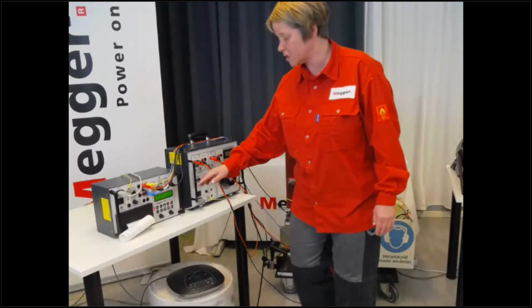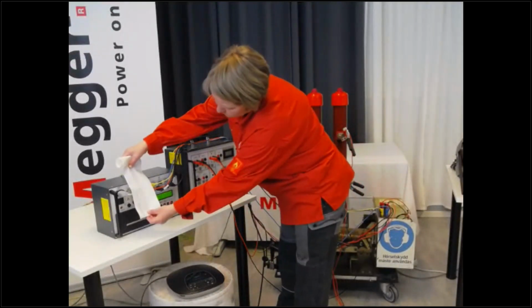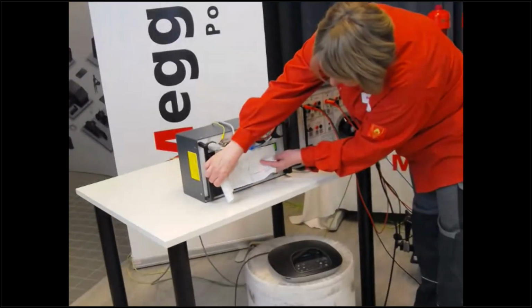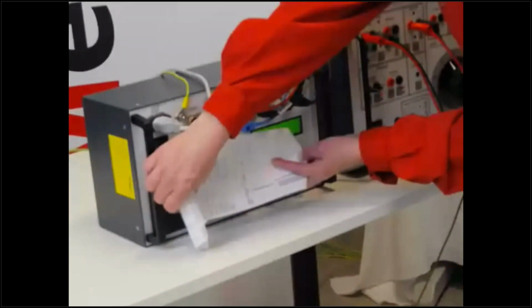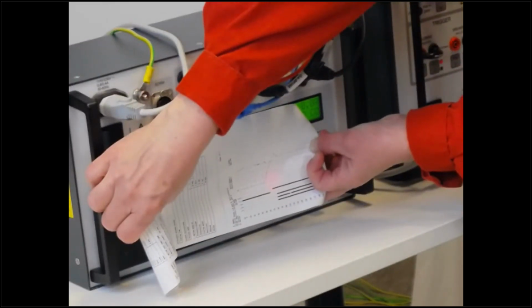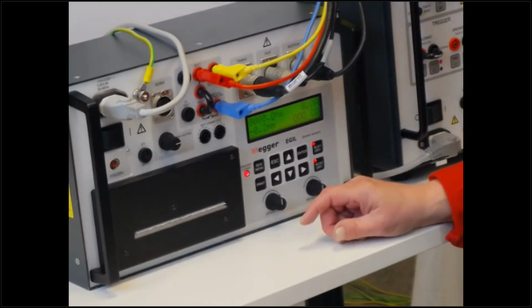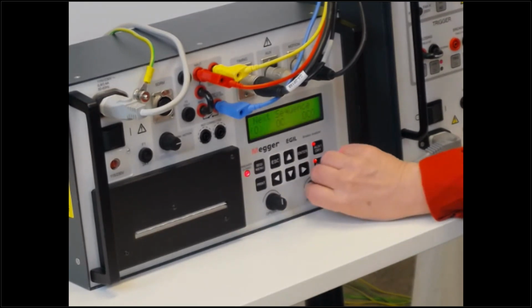One thing I didn't mention before is that the EGIL supplies either from coil or from motor. So you have to switch in between. The coil current is very, very small, as we mentioned before, and the motion, yeah, it's a normal slope, I would say. We continue with the sequence. I'm going to move back to the sequence menu and do an open operation.